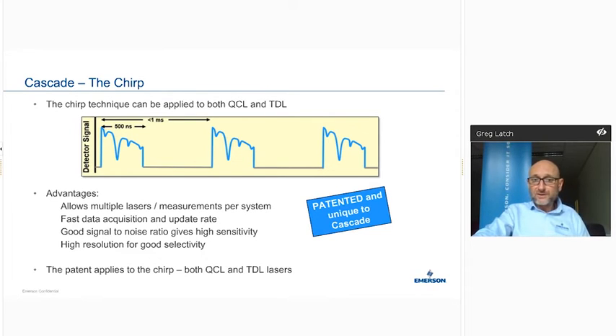The chirp technology is embedded within the analysis in its own right. I think I've probably explained a lot of that, but as you can see, the speed of response is very, very rapid. My terminology, it is a little bit like a machine gun scenario. We actually emit multiple photons. We look over a very small wavelength period, or multiple wave numbers. As you can see there, you're talking, for example, less than 1 millisecond between the chirps. You can see some of the resolution, some of the absorption that's carried over. So to give you a snapshot, rapid analysis, for example, up to 10 hertz.